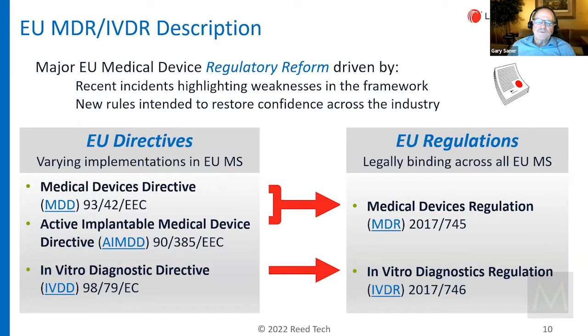This is quite different from the way the FDA rolled out UDI in the US. FDA simply layered on an additional requirement for UDI. All the other approval processes, the registration of establishment, listing and everything for products, there was no change. It did not touch any of those rules. It just said, by the way, you also have to do UDI. That's not the situation in Europe.